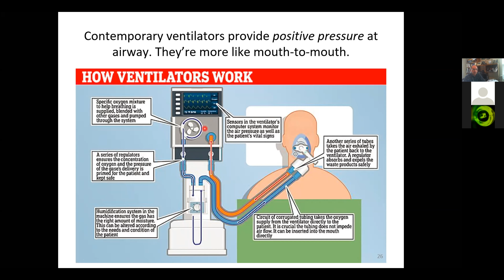The oxygen blender provides the dialed-in concentration of oxygen. The pumping system regulates the pressure and the flow. There's humidification. The gas is bubbled through water so that the inner airways don't dry out. And there's a sensor and monitor structure that, in part, what's shown here mostly is electrocardiogram. So in part, it's monitoring the patient, but really much of it is monitoring the electronics of the ventilator. The ventilator has to have its own fail-safe structure.